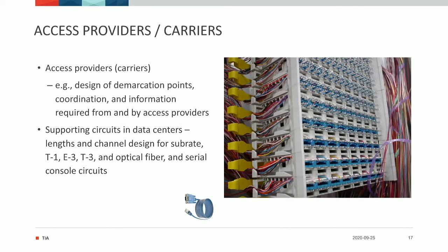There's a lot of supplemental information in the TIA-942 standard. There's a whole section on how to deal with your access providers or carriers, planning the demarcation points with them, coordinating them regarding the type of information they require, like the number of cabinets, how you should be terminating with them, and the type of cabling required. We also provide guidance regarding the length of circuits in data centers, such as T1, E3, and T3 type circuits. We have another section regarding the length of serial console cables in the data center.